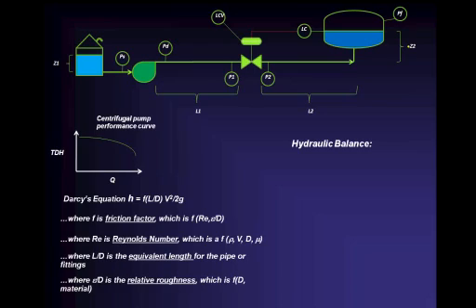Let's do our hydraulic balance, okay? We're trying to find out what our P1 and P2 are. I'm trying to help you understand how you do that so that you can tell your valve manufacturer what those numbers are. What is the suction pressure at the pump? In essence, let's say that's a short piece of pipe, this little green piece of pipe. It's almost infinitesimal. The suction pressure at the pump, therefore, is equivalent in feet to the head of liquid in the tank from which we get the suction. So that's the pressure at the suction of the pump, PS equals Z1. The discharge pressure of the pump is equal to the suction pressure at the pump plus the total developed head at any particular flow rate as determined by the performance pump curve. So it's PD equals PS plus TDH. You okay with that? I hope so.